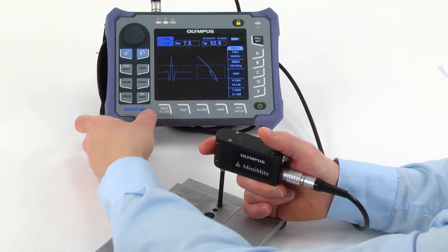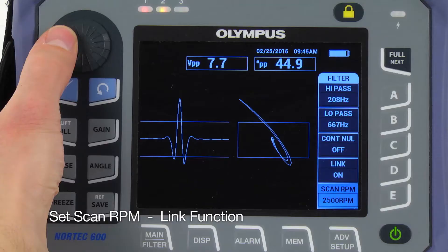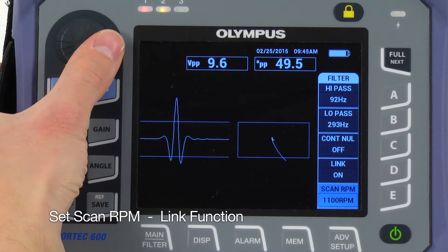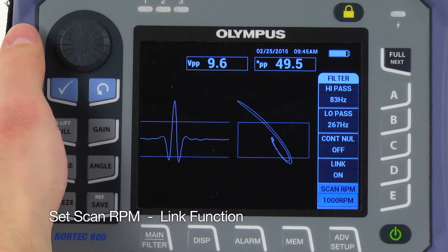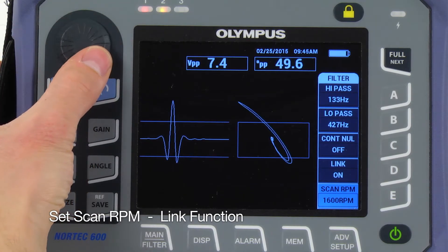Press the Main key and set the scan RPM to the desired speed. If the scanning speed increases or decreases, the link function automatically readjusts the filter settings to compensate for any change in RPM, so you don't have to do any manual filter adjustment.